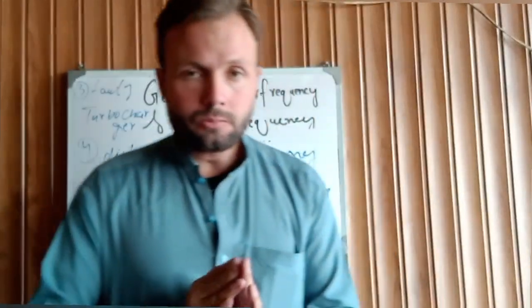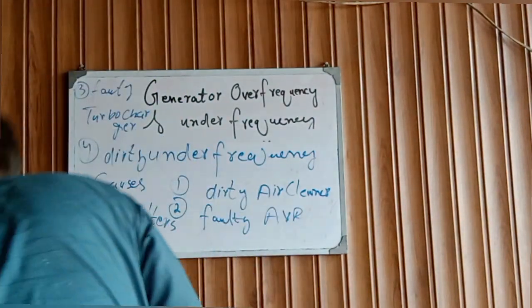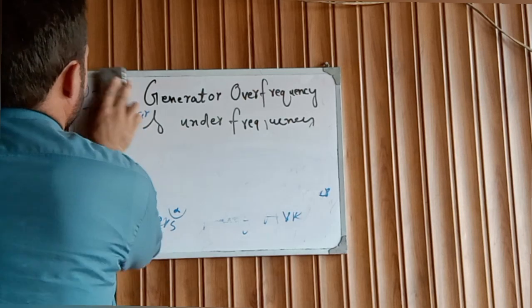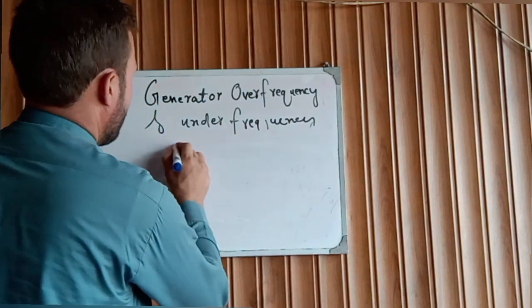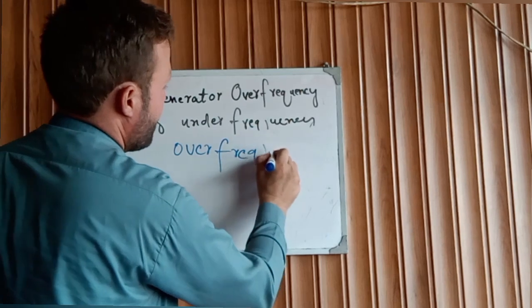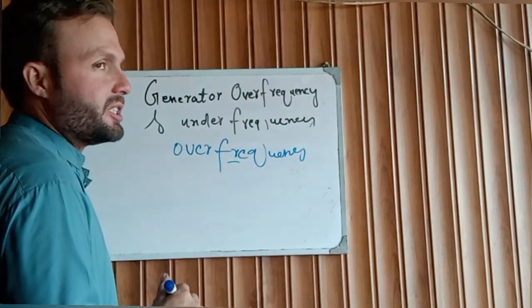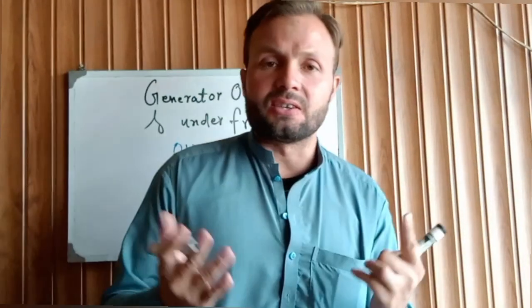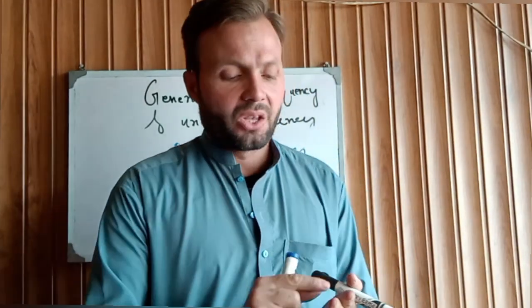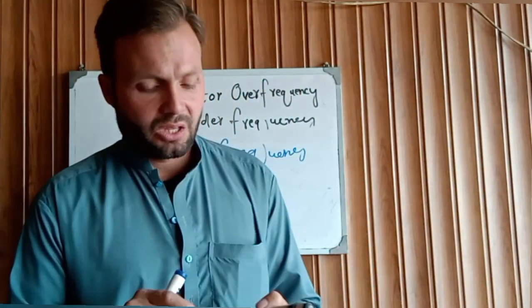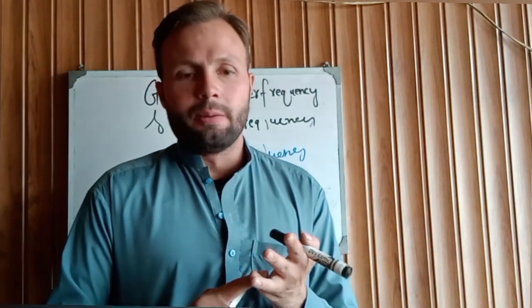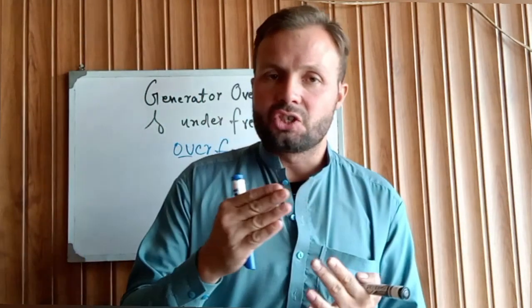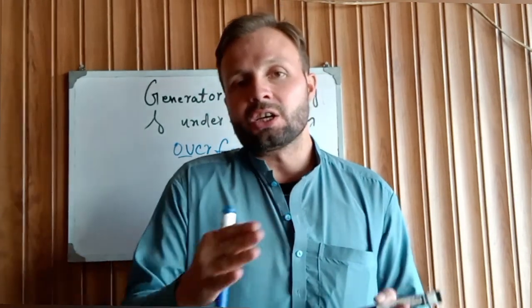Now let's talk about over frequency. Over frequency means your engine speed is higher than the rated RPM. Most of the time, a faulty governor causes the frequency of the alternator to fluctuate. The governor accelerates the engine too much, the generator speed increases, the frequency increases, and the generator goes to over frequency.